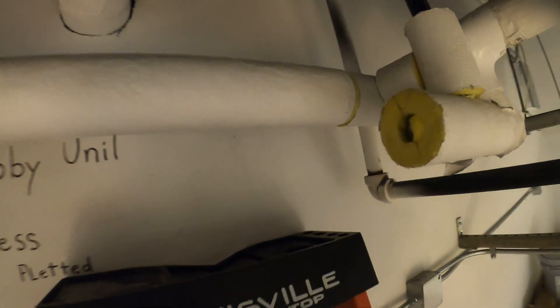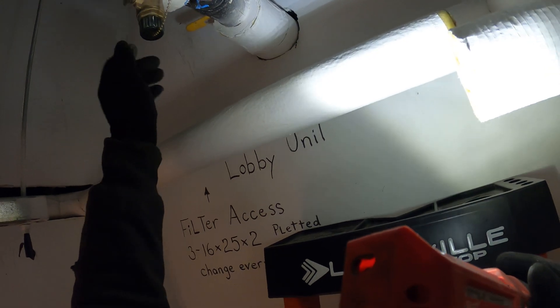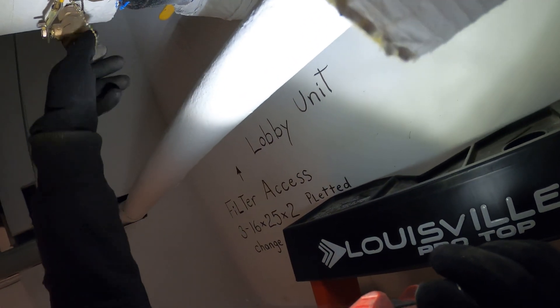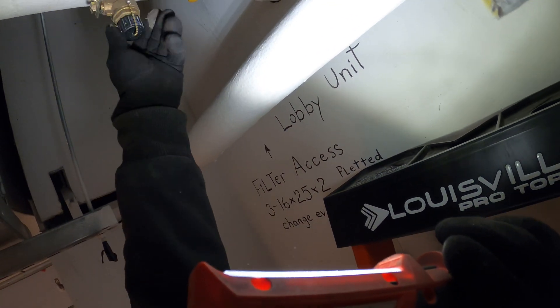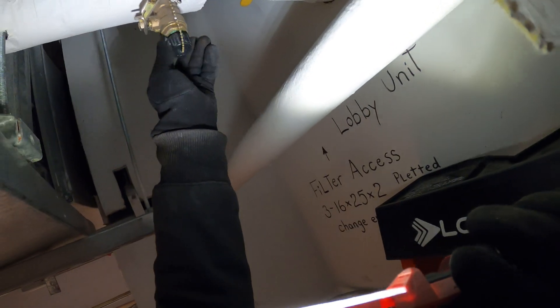So we're set up and I'd rather be on this ladder and safe to do this job. Alright, I shut the unit off on the thermostat and we're going to close our valves. Alright, so we got the valves closed and we're going to pick the lowest point here and we're going to drain this coil.